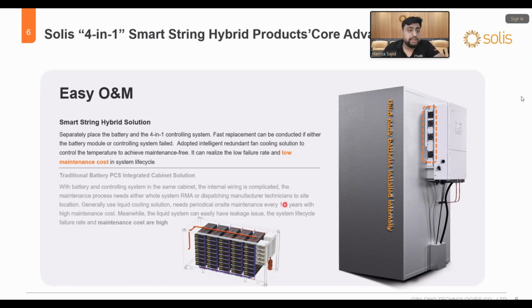With the battery and the controlling system in the same cabinet, the internal wiring is complicated. The maintenance process needs either the whole system RMA or dispatching the manufacturer technicians to the site location. Generally they use the liquid system. A liquid cooling system needs periodic on-site maintenance every 1 to 5 years with high maintenance cost, while the liquid system can easily have a leakage issue.